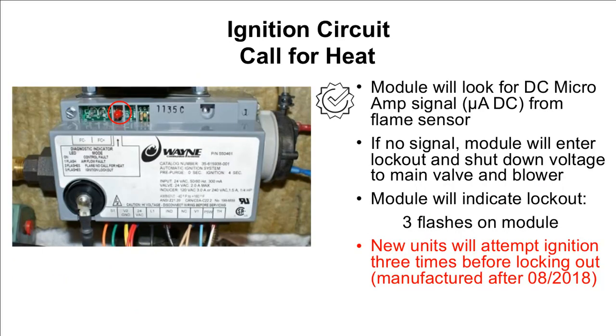The ignition module is looking for this signal. If it does not see the signal, it will enter lockout and give you a 3-flash code on our LED. I'd also like to mention that from August 2018, we did make a modification to this module. It will try to ignite 3 times. So it will start the blower, it will attempt ignition, it will continue the blower running for 30 seconds after a failed ignition before trying again.